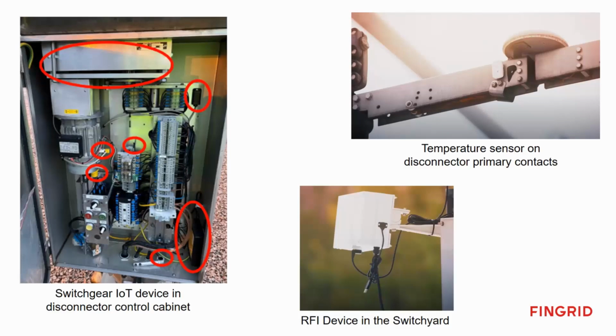So the system is measuring every single operation that this disconnector is having over time. Then on the bottom, that white color box is the radio frequency interference device. It's mounted on a pole in the switchyard, and the antennas are mainly directed toward the instrument transformers, but it's measuring the radio frequency radiation in all the surroundings.